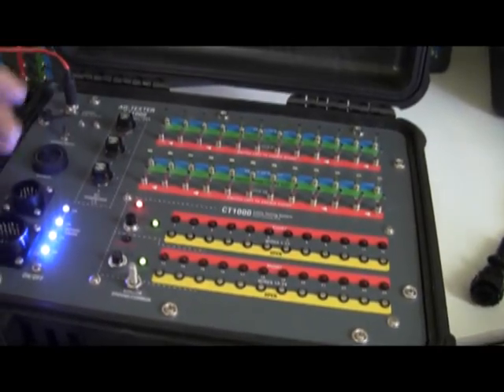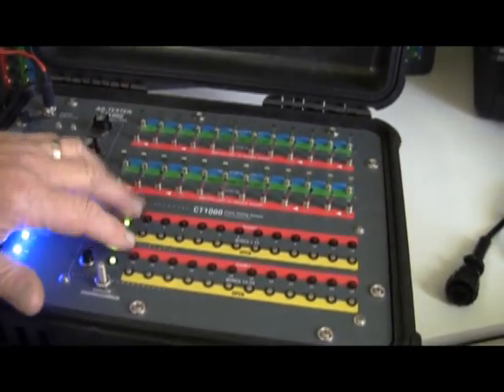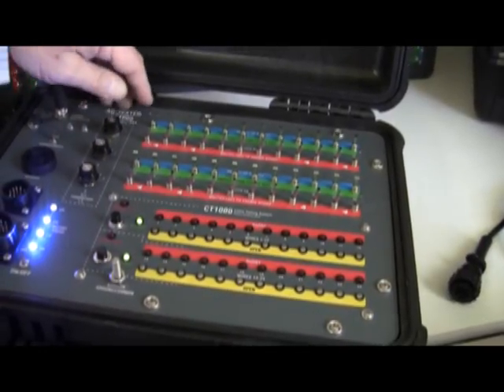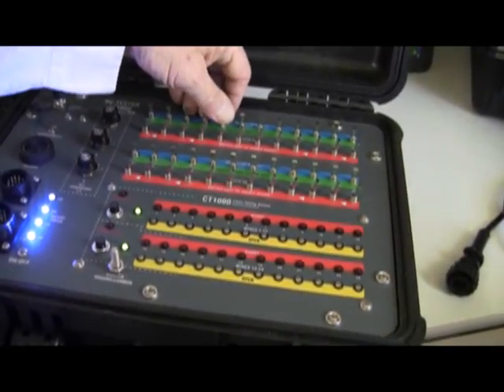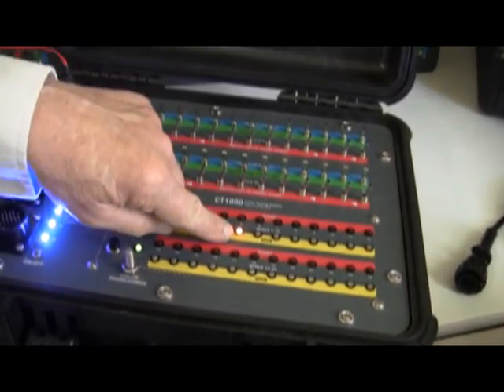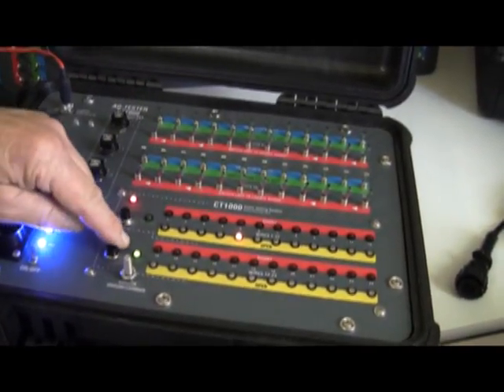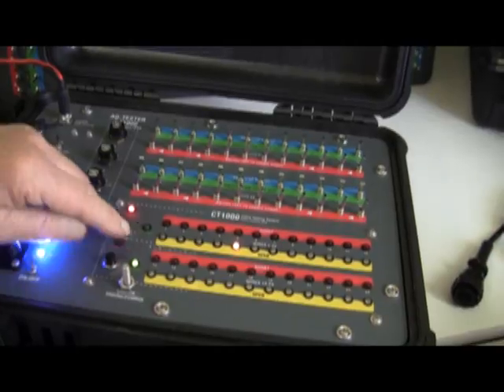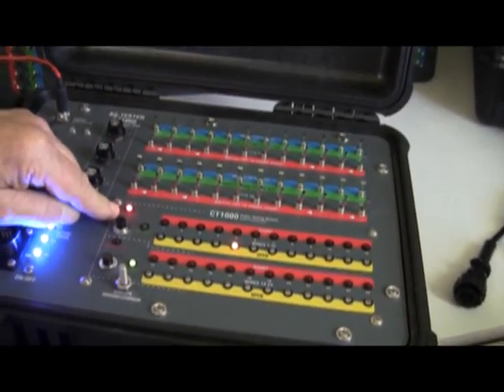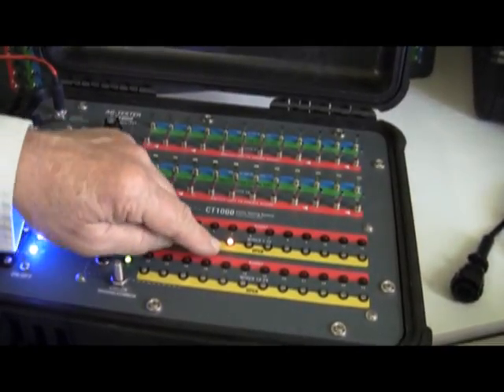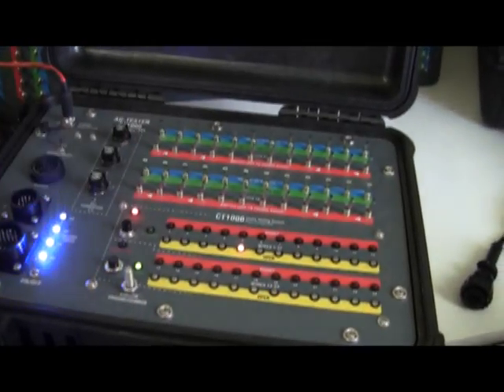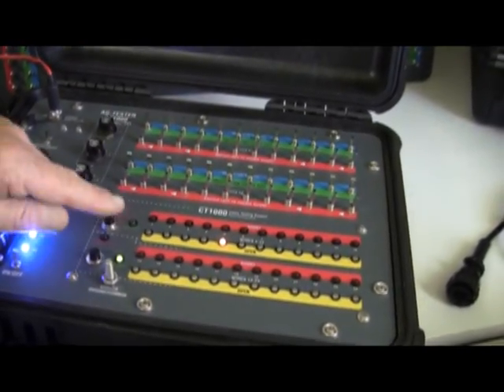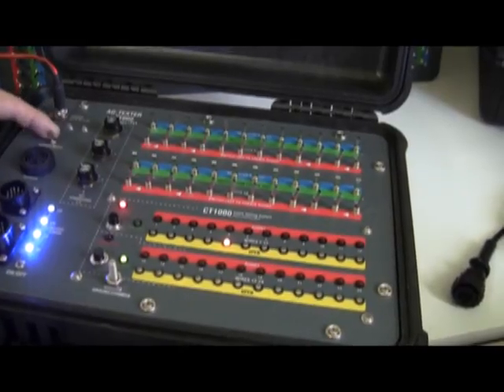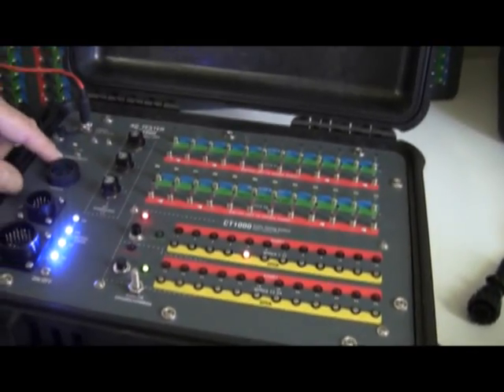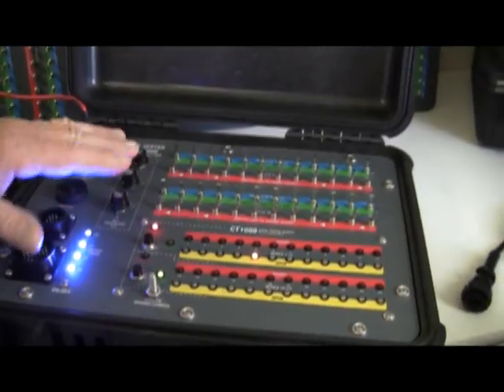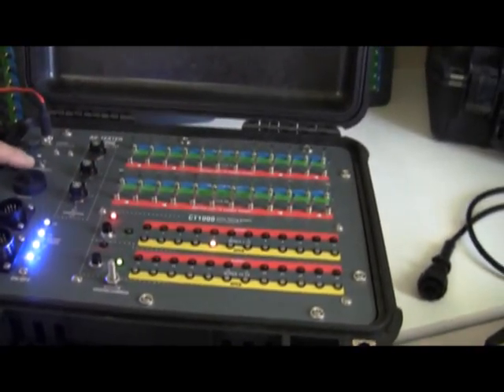I had the sounder shut off, so let's start over from the basic condition. If I put an error on wire number 5, light number 5 shows up, the all-okay indicator goes out, and the alarm LED comes on. Wire 5 shows as an open circuit since there's no connection. Now I can turn off the sounder using the sounder on/off switch, so we can continue testing without listening to it.